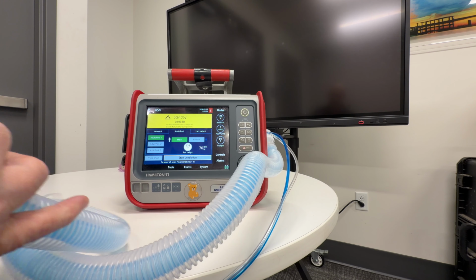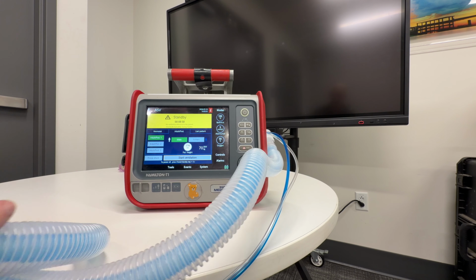So now we're going to do the pre-op check. So the way that you're going to do this, you're going to start off in this position. You're going to have the flow sensor pointing out like that, and these tubings are going to go down. So we're going to connect it up just like this. We're going to go to pre-op check. We're going to go to flow sensor, and we're going to start the test. It says disconnect patient. We don't have it connected. It says flip flow sensor. You're going to take it out right here, flip it over there.